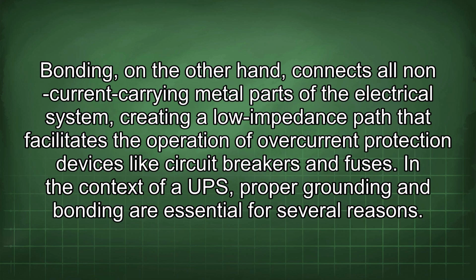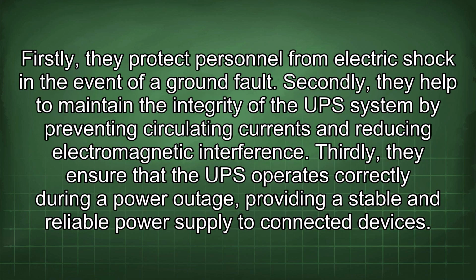Bonding, on the other hand, connects all non-current carrying metal parts of the electrical system, creating a low impedance path that facilitates the operation of overcurrent protection devices like circuit breakers and fuses. In the context of a UPS, proper grounding and bonding are essential for several reasons. Firstly, they protect personnel from electric shock in the event of a ground fault. Secondly, they help to maintain the integrity of the UPS system by preventing circulating currents and reducing electromagnetic interference. Thirdly, they ensure that the UPS operates correctly during a power outage, providing a stable and reliable power supply to connected devices.